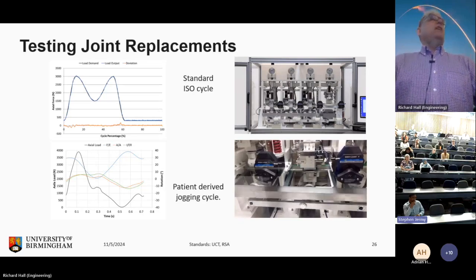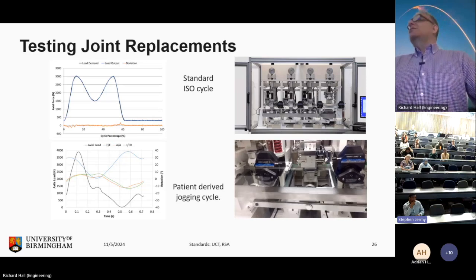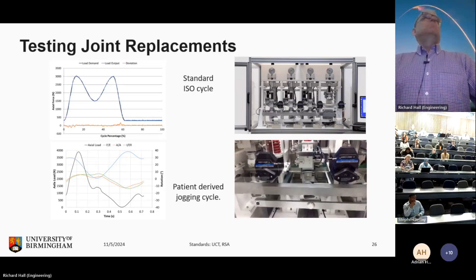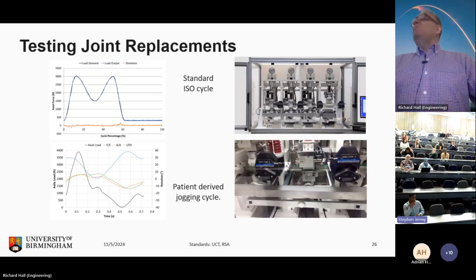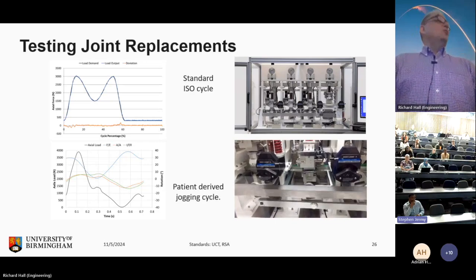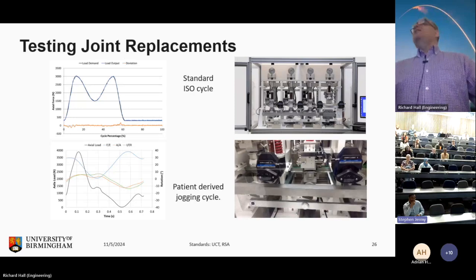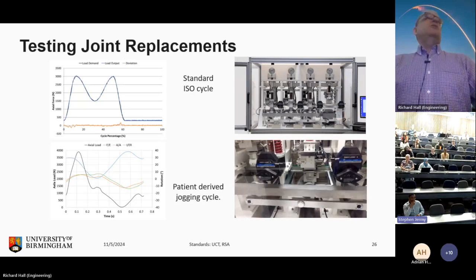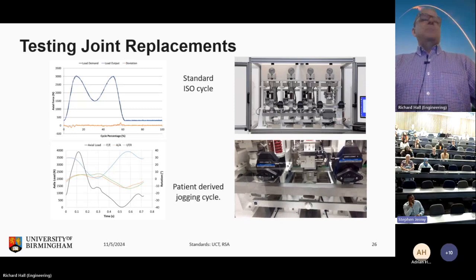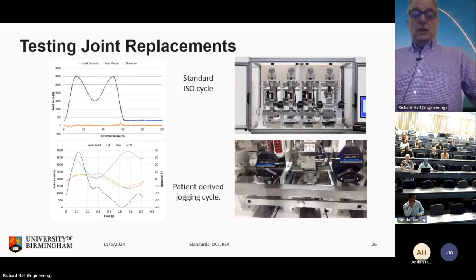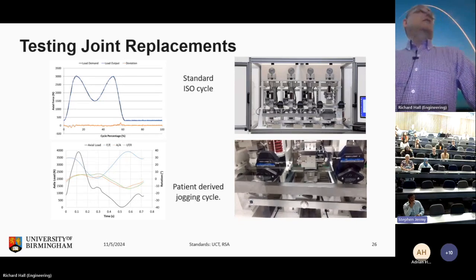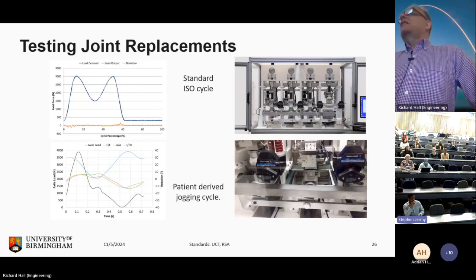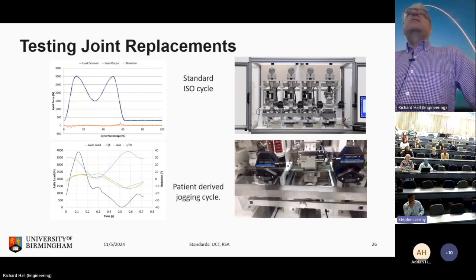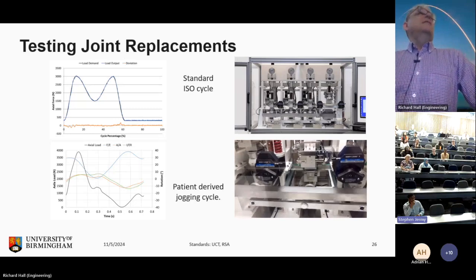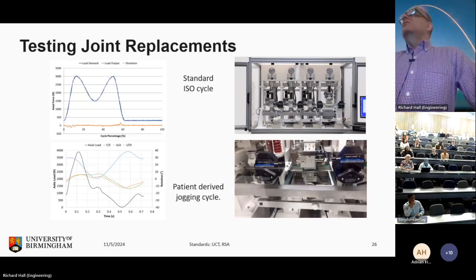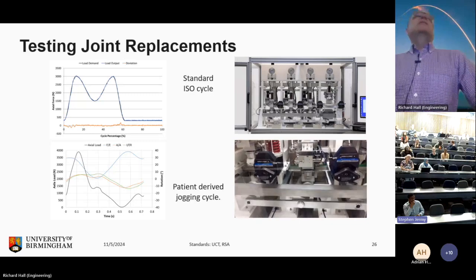So these will run for, let's say, typically 5 million cycles. Does anybody actually, for 5 million cycles, just walk? Well, that's the benchmark. That is the absolute benchmark for a total hip replacement. Yeah. The diagram below and the figure to the left is actually for a jogging cycle that you can run on our machines. And they generate a different set of data than you would do through the standard ISO cycle.